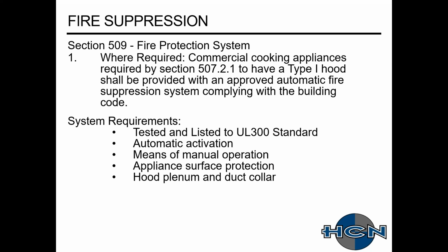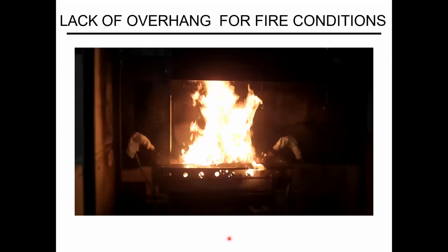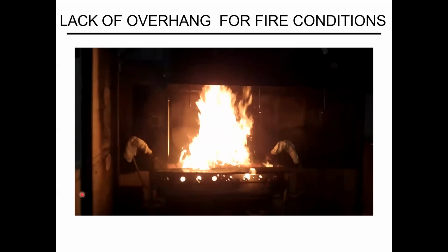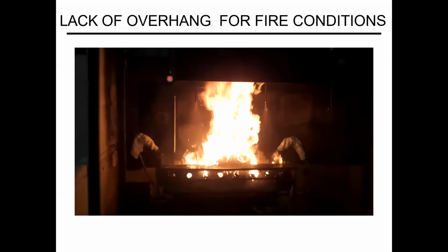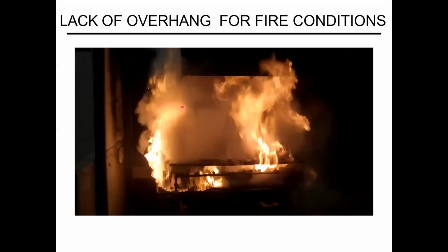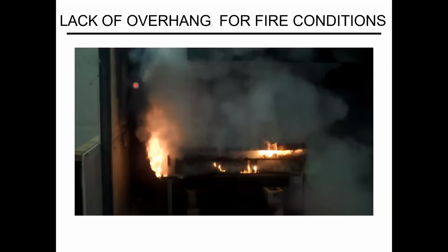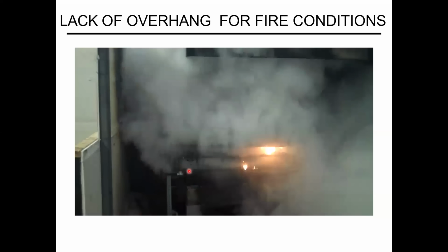So I kind of touched a little bit on the design of end panels. If we were using end panels, this is a big thing why I say quarter end panels are great, but if you can utilize regular end panels, it's going to benefit you a lot more. Here's the edge of the hood right here. Fire system activates. You can see that wall is catching on fire. So by utilizing an end panel right there, that would actually keep that fire from expanding and hitting that sidewall.